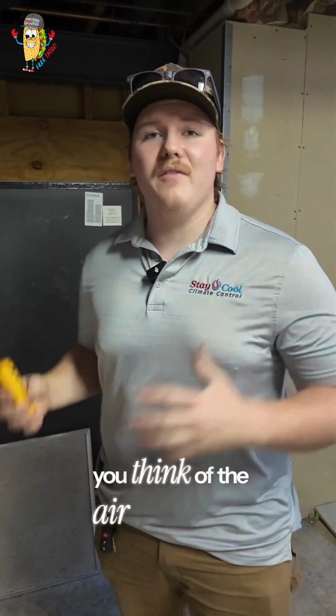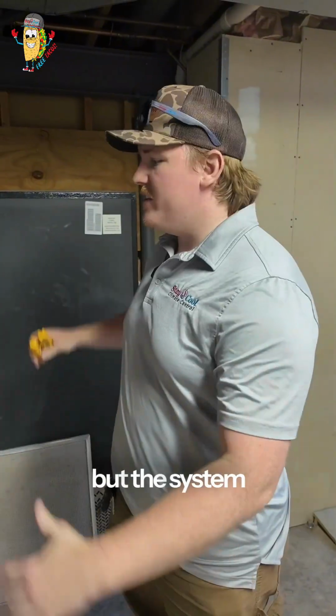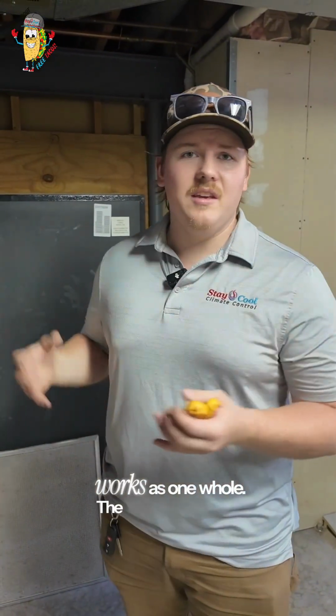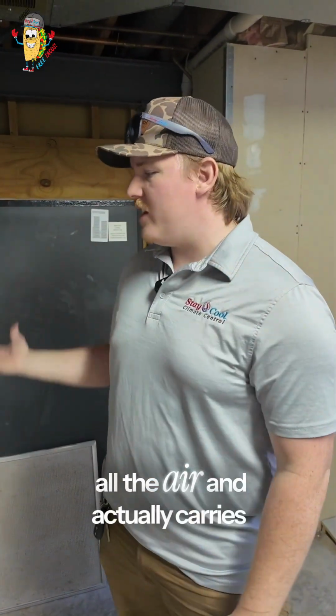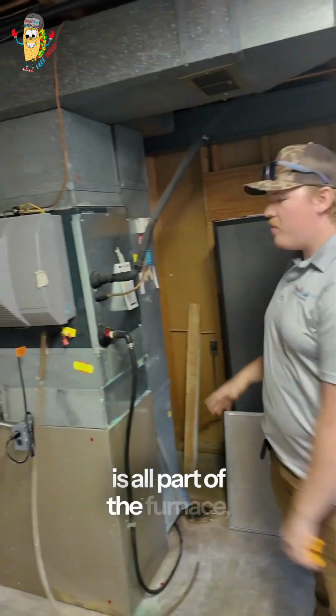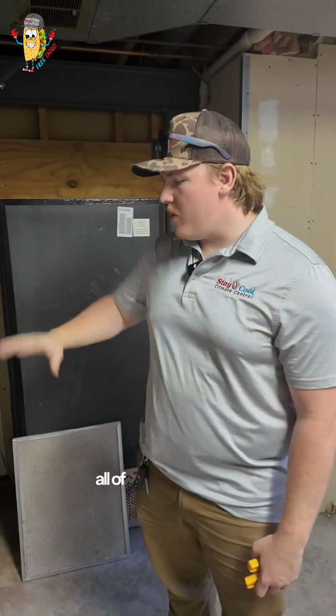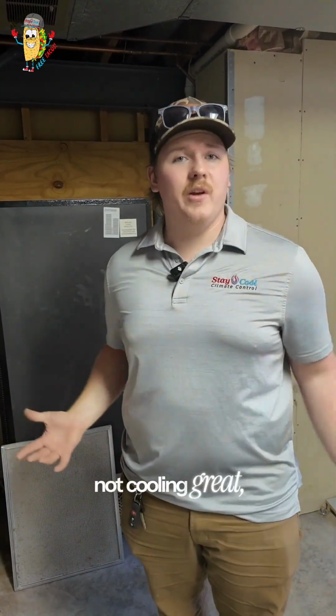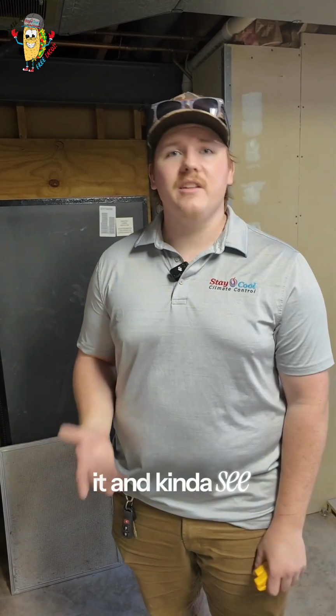Now, normally when you think of the air conditioner, you think of the big outside unit with the fan spinning, it's real loud, but the system actually all works as one whole. The fan that distributes all the air and actually carries that cool air into the house is all part of the furnace. So that's where we start our inspection. We check a lot of the same things that we check with the furnace. We check our temperature drop, all of our components, make sure the air is working good. This system right now is actually not cooling great, so we're definitely gonna wanna get some gauges on it and see what's going on.